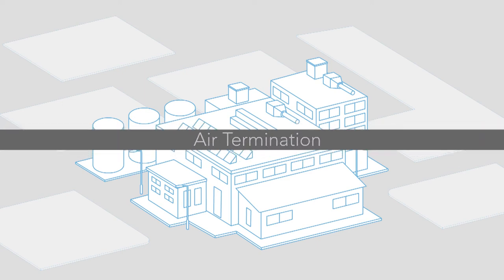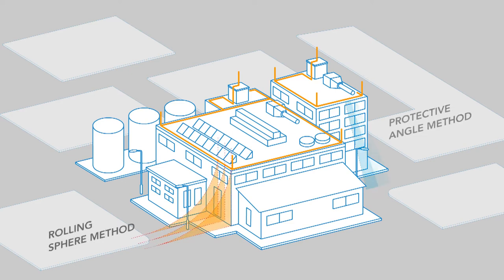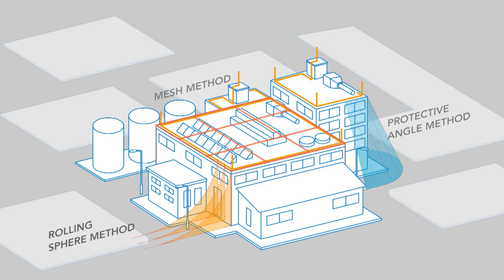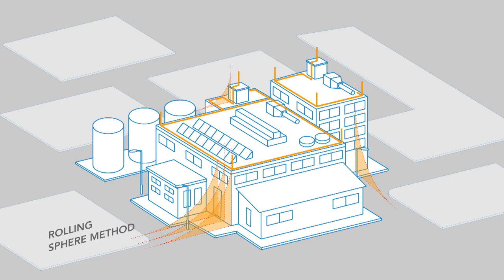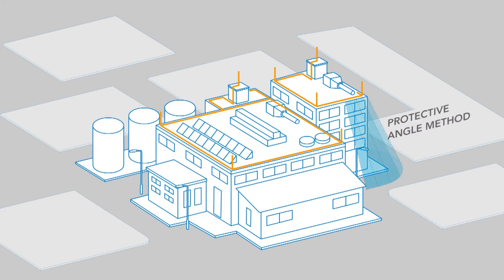Air Termination: The positions of the air termination can be decided based on the rolling sphere method, the protective angle method, and the mesh method. The rolling sphere method can even be used to define the zones of protection for structures with complex geometry, with the radius for the sphere determined directly from the class of LPS. The protective angle method is used for simple structures, but only up to a certain height as determined by the class of LPS.